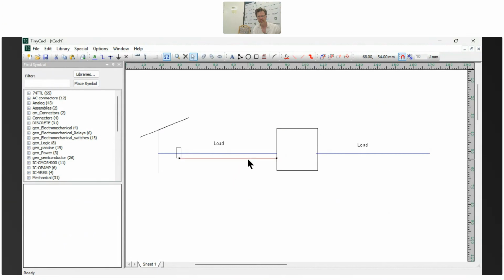comms going back to it. And so if I had it set to zero export to load, because this is the load terminal, and then we have like the grid terminal is the input terminal. So if it was zero export to load, it would only support the loads on the right-hand side here. It wouldn't try and offset the loads on the input side. So any loads you had on this side would be running off the grid.